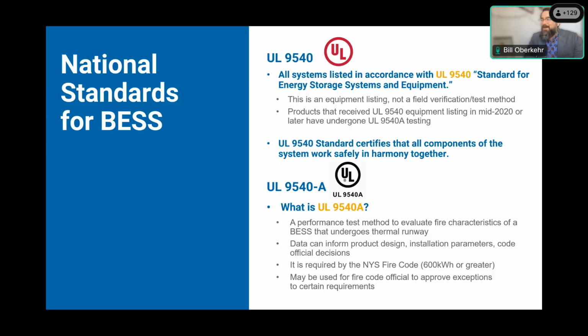I'm going to quickly go through the difference between those two things. UL 9540 is an equipment listing. That's a stamp, an approval. It's a yes or no, binary. What UL is saying by issuing the UL 9540 equipment listing is that all of the components of the system work safely in harmony together, that this unit, as a unit, has been tested with all of those components in place, and there is no additional or unnecessary hazard caused by this equipment being used in conjunction with the rest of the system. So again, that's binary. You either have the UL equipment listing or you don't. There is no in between.